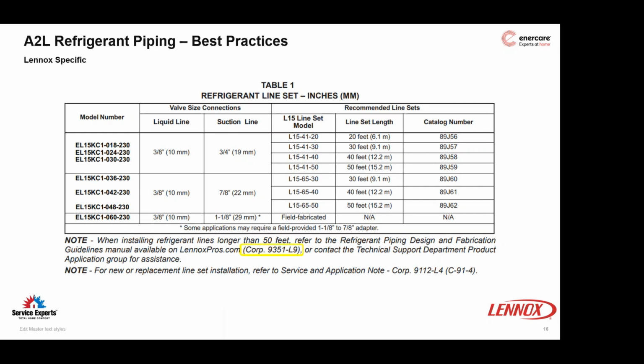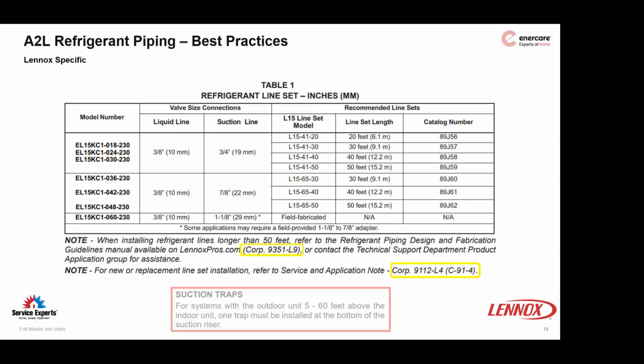Now, Lennox does have additional documentation for anything beyond 50 feet, for their piping and design guidelines, and they offer a couple of suggested piping practices within another document as well. I think this was the same as the 410A, because this comes right out of the 410A design manual. This is the one they're directing you to, for anything where your line set rises any more than 5 feet to get outside to your outdoor unit.